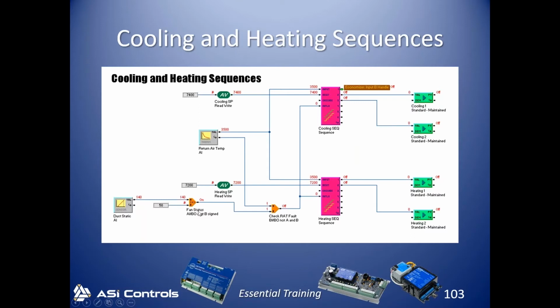And so there's all kinds of different logic types. And so this type is AI/BO, which means there are analog inputs with a resulting binary output. And the binary output will turn on, in this case, if the A value, which is the upper value, GT, means is greater than the B value, which is the lower value. And it's what we call a signed comparison, which means negative values are allowed.